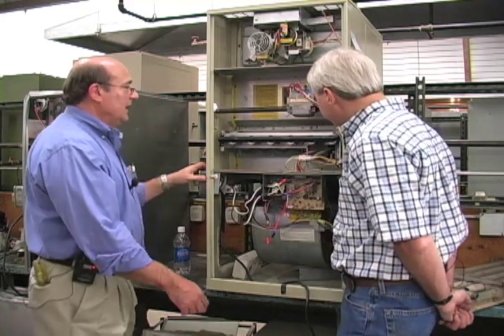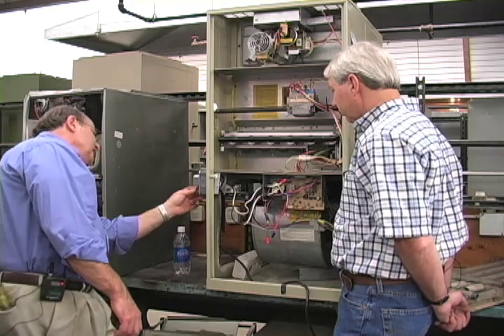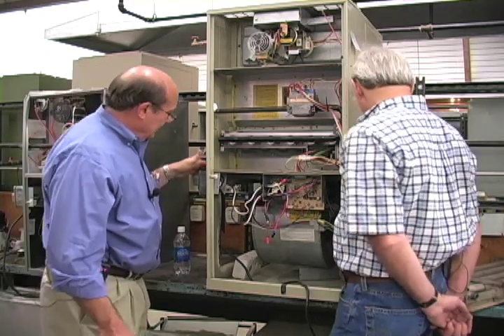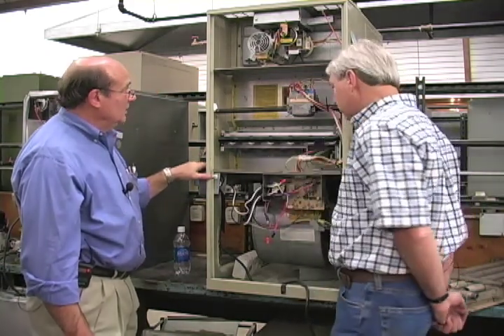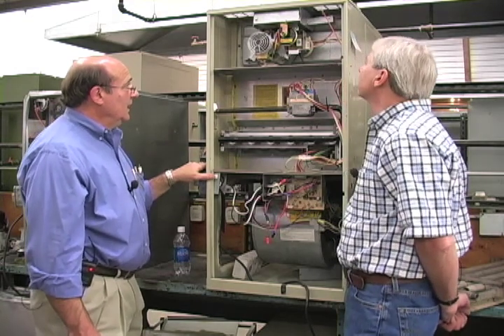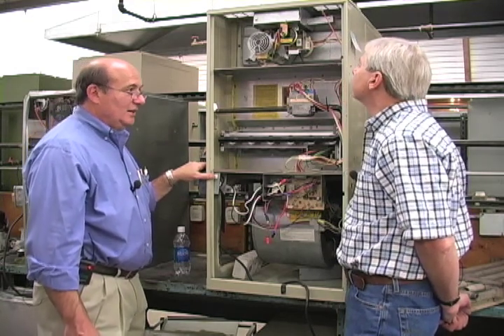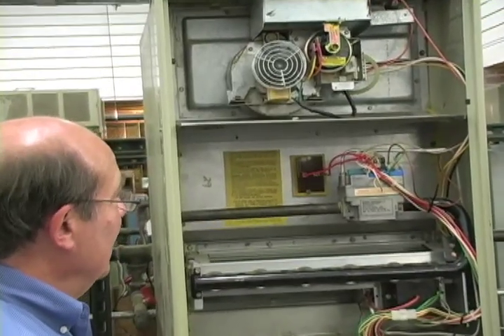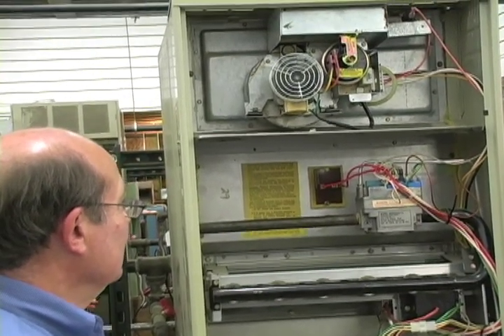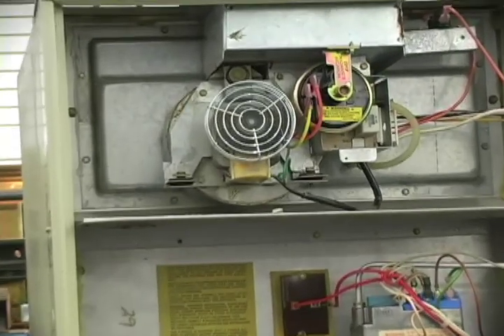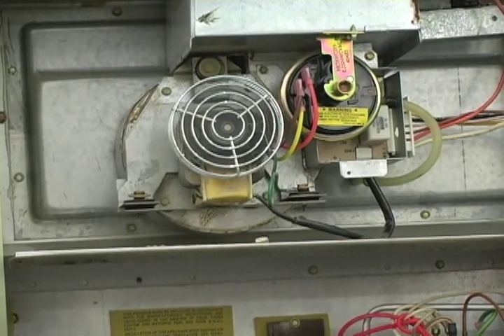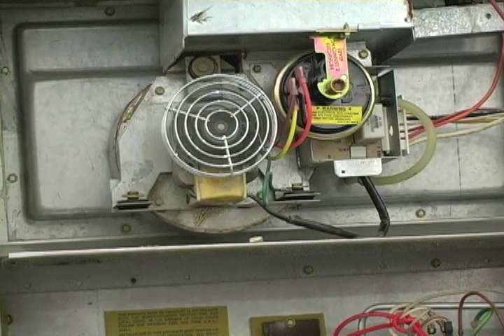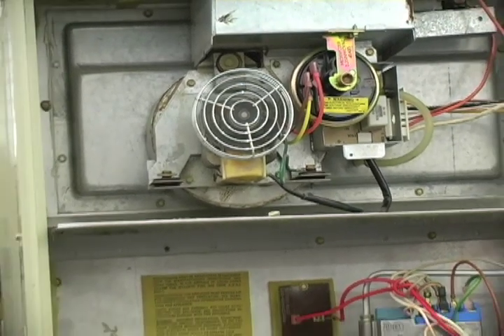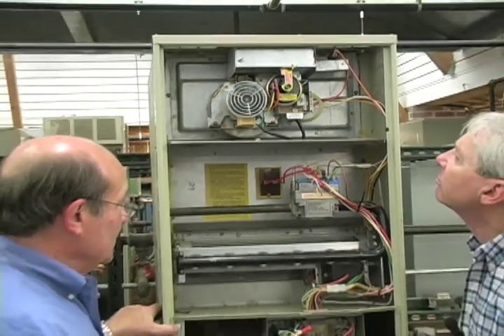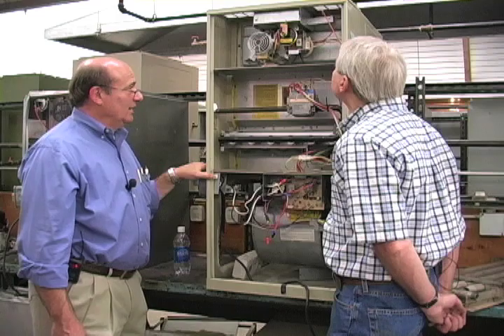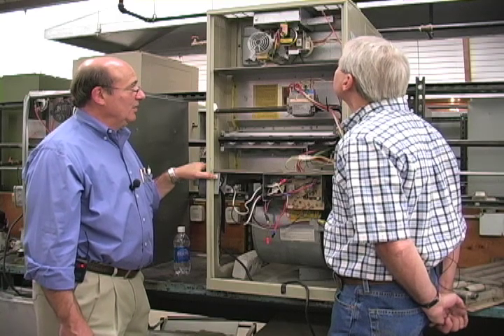So we've got power at the furnace here. We've got it plugged in over there. And we'll go ahead and close the door. There you go. Boy, that's a terrible sounding combustion blower motor. That thing's about ready to fail. It's got a bearing problem, a sleeve bearing problem, or just worn out. That's something I would be looking at as a furnace inspector. We've got an older style furnace here with a bad or an imminent failure in the combustion blower motor.